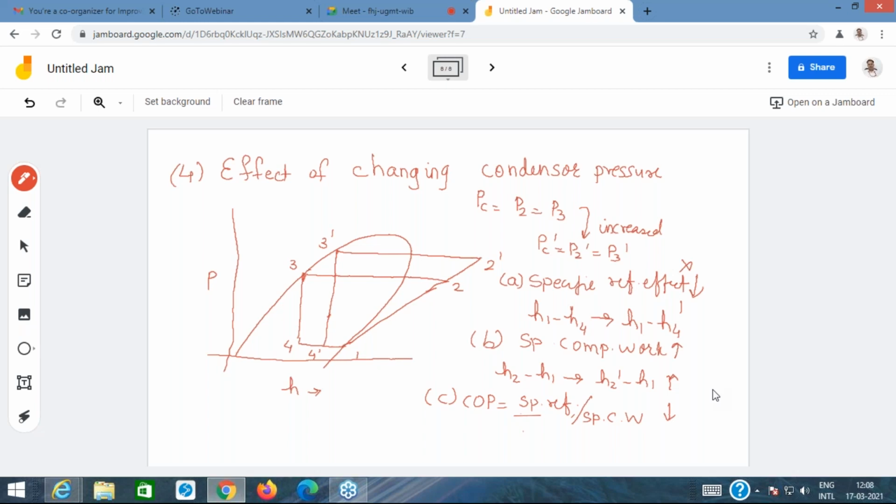There are some practical things, for example, you need to maintain the condenser. If there is a utility and it is not maintaining the condenser properly, the performance of the condenser will degrade. If you are not maintaining the water quality, there would be scale formation on the condenser, and that would result in a decrease in the coefficient of performance. And what does a decrease in coefficient of performance mean? It would mean, in practical terms, an increased energy bill, which obviously would not be desirable. That is our job. The job is to see that the systems operate efficiently.